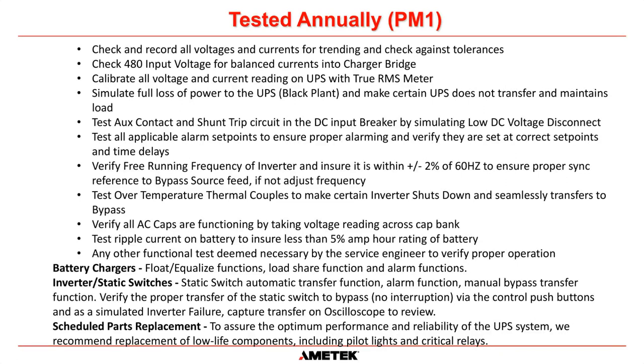So for example, let's say the tolerance for our input is 480 volts plus or minus 10%, just for ease. So that would be 48 volts below would be 432 volts, and 48 volts above would be 528 volts. So if the parameters of the AC input to that system were outside that tolerance, then we would note it in the report and make sure that the plant knew that the AC input for that UPS is out of tolerance, and they would need to go and retap the transformer or do something to make sure the input is closer to 480. And that applies to every other voltage, whether it's bypass, the DC voltage. We check all of those parameters against what they should be, okay?